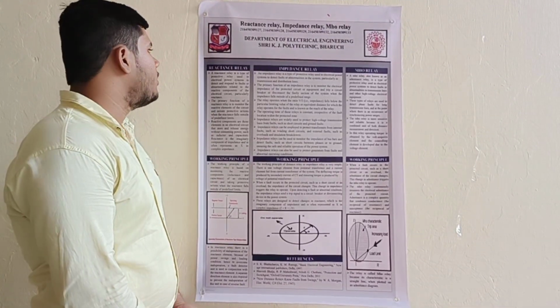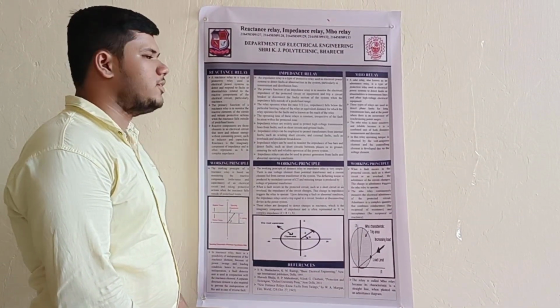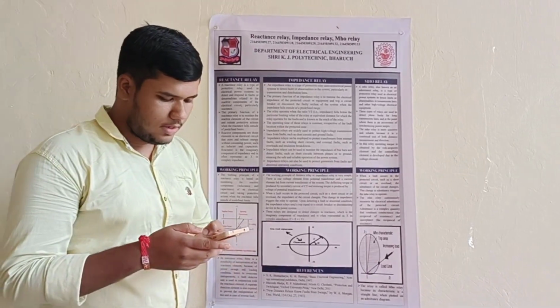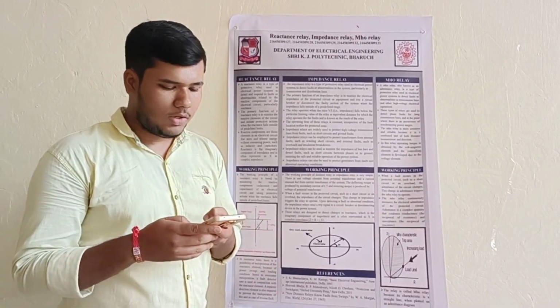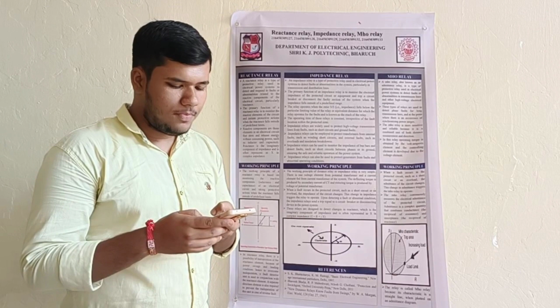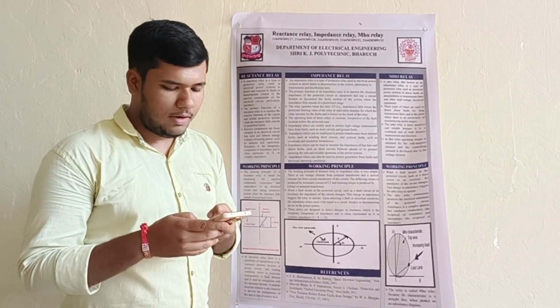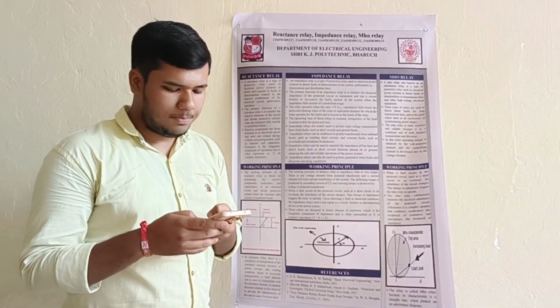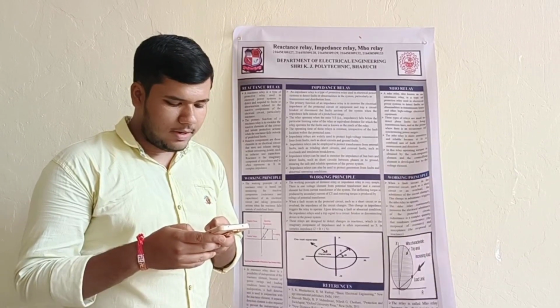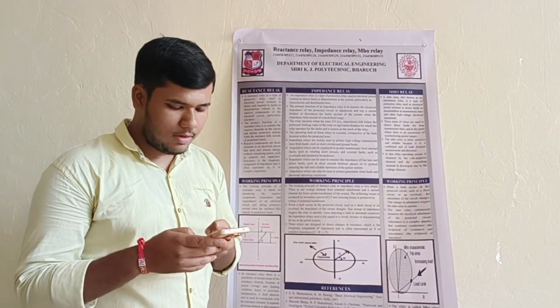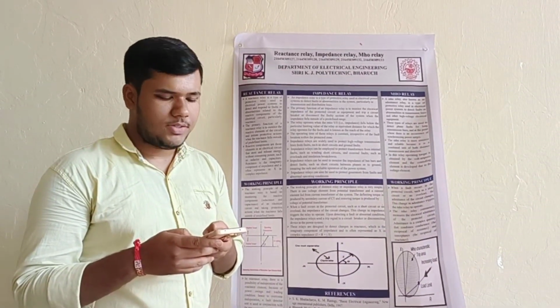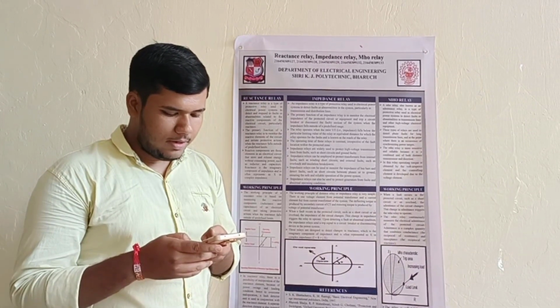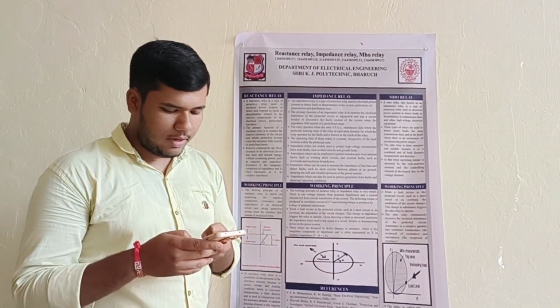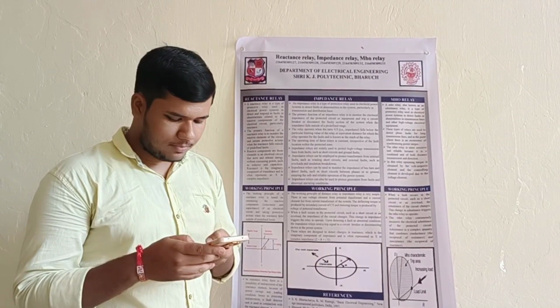Okay. Now our continued topic is reactance relay. In reactance relay, the operating torque is obtained from the current and the restraining torque by the current and voltage of the directional element. This implies that reactance relay is an overcurrent relay with direction restraints. The directional element is so designed to give maximum torque angle of 90 degrees.